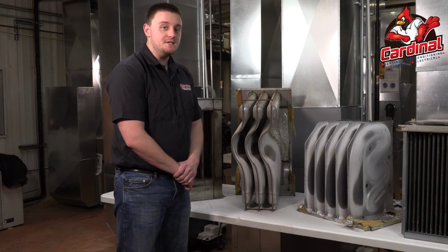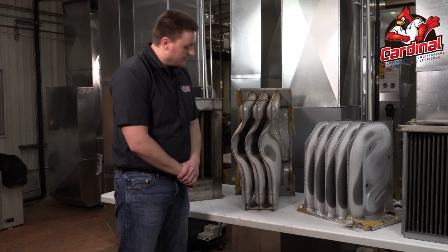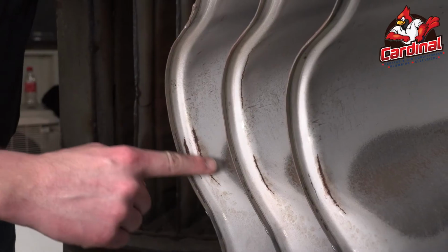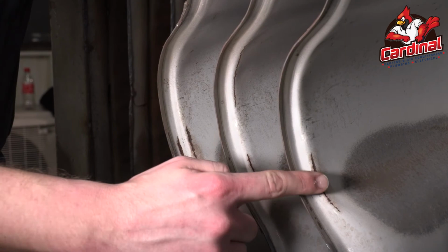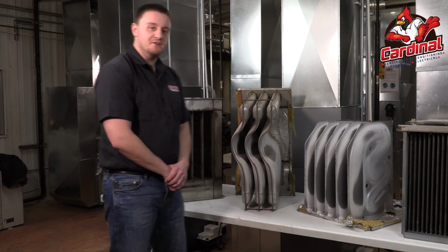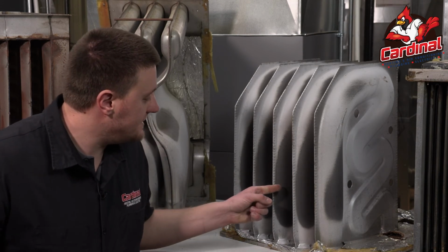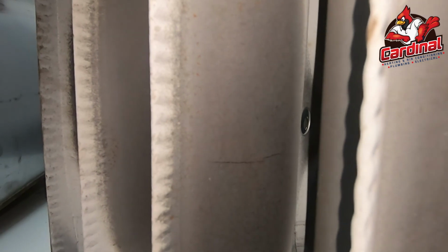Next up, this heat exchanger has a crack in each cell. You can actually see them right here, here, and here. Those are pretty common to find. This heat exchanger only has one failure and it's a crack right in here. Very hard to see, and even though there's only one failure in the system, we need to shut it down. Whether there's one failure or 10, it doesn't matter. Safety is really important to us and we want to make sure your system is running right. We also want to make sure that your family is safe.